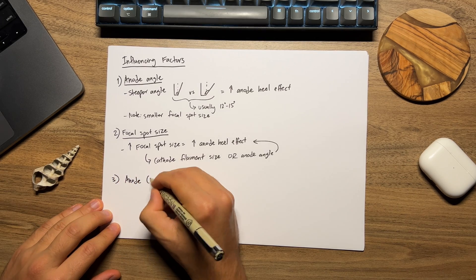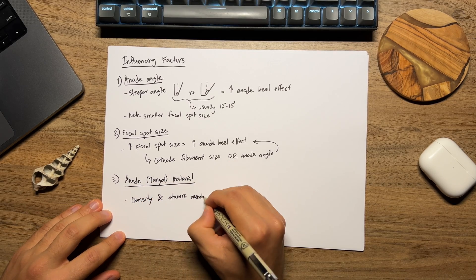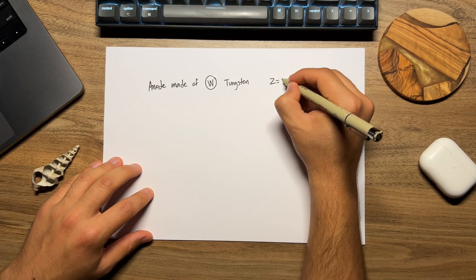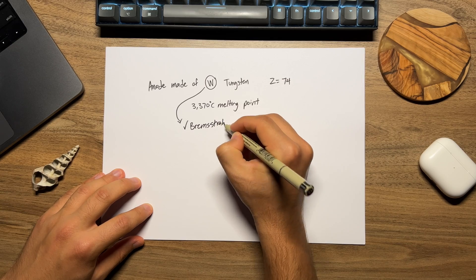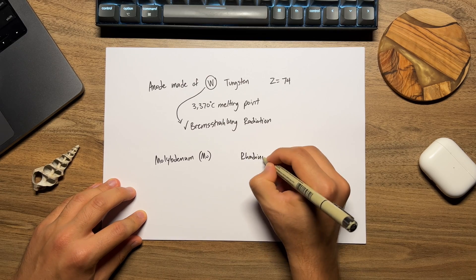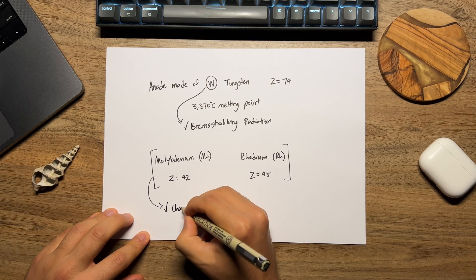The third thing that affects the anode heel effect is the target material — what the anode is made of. The density and atomic number of the anode material affects x-ray absorption. The anode is usually made of tungsten, which has an atomic number of 74 and a very high melting point of 3370 degrees, making it suitable for Bremsstrahlung radiation production. The anode can also be made of molybdenum and rhodium, with atomic numbers of 42 and 45 respectively, which are mainly used in mammography units as they're better at producing characteristic x-rays. This factor is relatively minor and not really what we focus on for the anode heel effect.